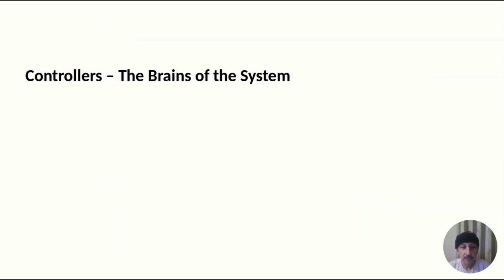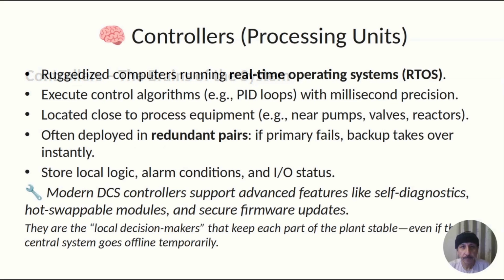Controllers, the brains of the system. Controllers are the unsung heroes of the DCS. They're not general-purpose computers. They run real-time operating systems optimized for deterministic response. When a temperature sensor spikes, the controller must react within milliseconds, not seconds. That's why they are hardened against heat, vibration, and electrical noise.